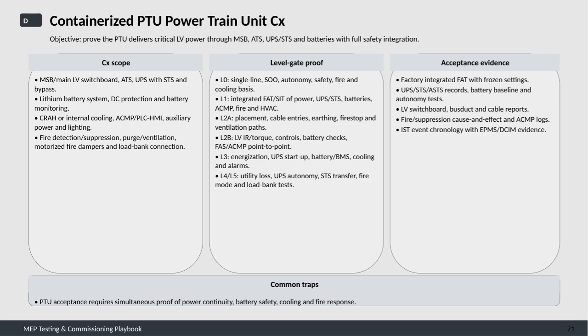Our acceptance evidence includes factory acceptance tests with fixed settings, detailed records from UPS and transfer systems, baseline battery tests, as well as reports on switchboards and cable assemblies. Fire suppression cause and effect logic and operator control monitoring logs are reviewed, alongside a comprehensive event chronology, supported by emergency power management system data. One common challenge during PTU acceptance is the need to simultaneously validate power continuity, battery safety, cooling performance, and fire response. Balancing these aspects requires careful coordination and thorough testing to ensure everything works seamlessly together for reliable emergency power delivery.